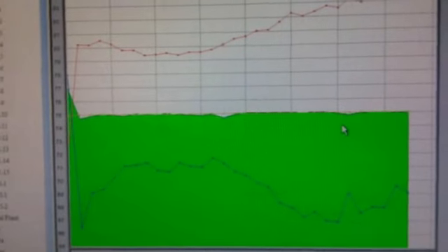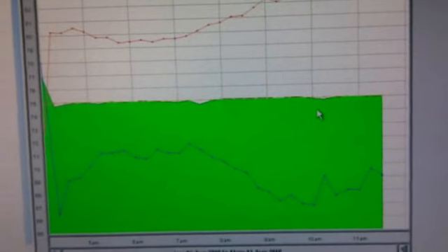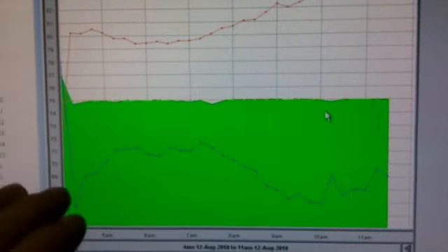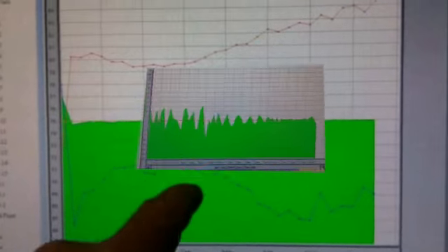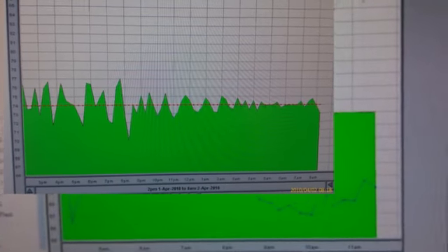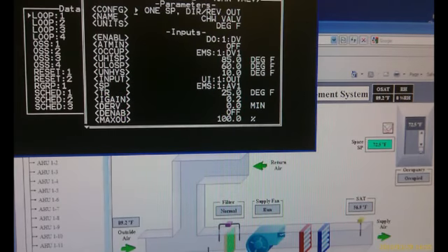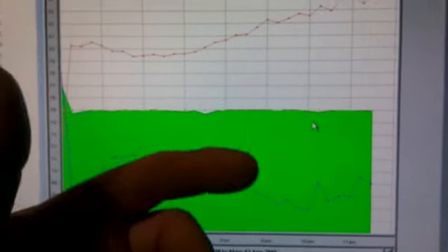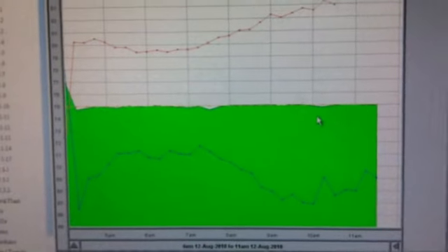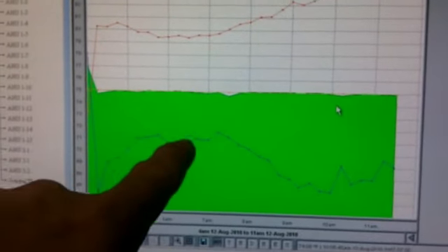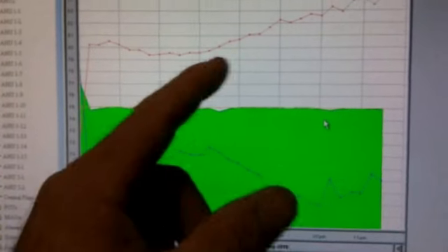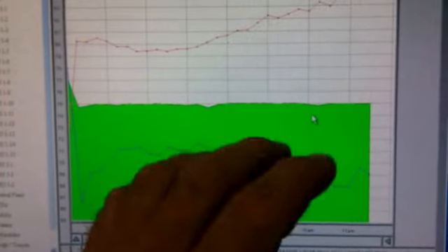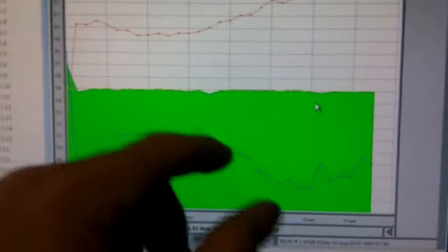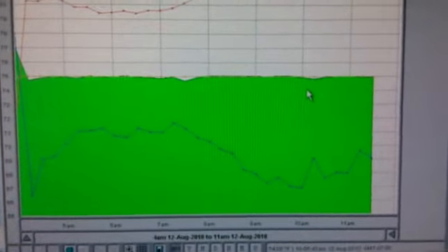That's tight. So I got some of, not all of them I got working that good, but some of them pretty tight. So instead of on-off, which is the way that a lot of these were before I started changing some actuators and recalibrating them and reprogramming the loops, they used to go on-off. Some of them even would overshoot and switch to heating and then overshoot and switch to cooling. It was pretty screwed up. But now it's just adjusting the supply, steady output, just to oppose the outside air mixed in with the fresh air, and also whatever the heat load happens to be in the room, going off of what the space is.